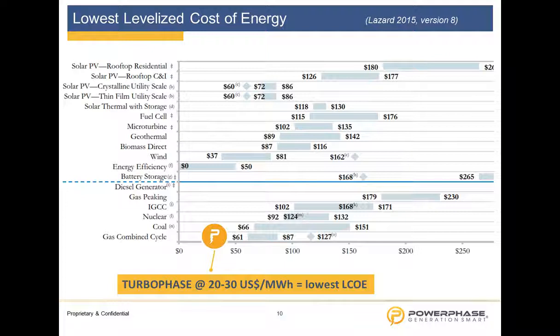And when we run the same metrics with Turbophase over the same life cycle costs, what we find is the operating costs per kilowatt hour or megawatt hour are about half of what your combined cycle is. And so this allows us to show to customers what the operating costs and the net benefit between the capital and the OPEX and the fixed O&M costs are for the product. And these take into account net power.